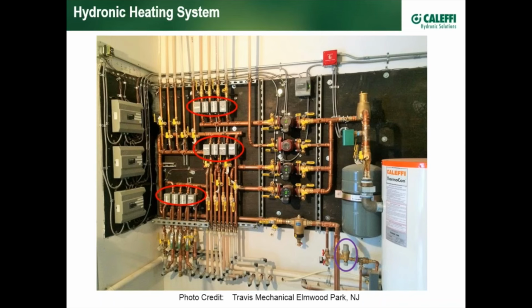Controlling those zone valves and controlling these secondary circulators, by the way, are over here in green, Caleffi's line of zone relay controls. We didn't speak about that today, but if you have an interest in these products, please contact your Caleffi rep. Very successful product in the marketplace. Up here top right, Caleffi's line of coalescing air separators. Not only are they very efficient at ridding a system of any air, but also are extremely reliable because of the high quality components. Down here, going back to the boiler, Caleffi's dirt separator, and in this case, a magnetic dirt separator that is especially adept at taking out that tricky debris called iron oxide.